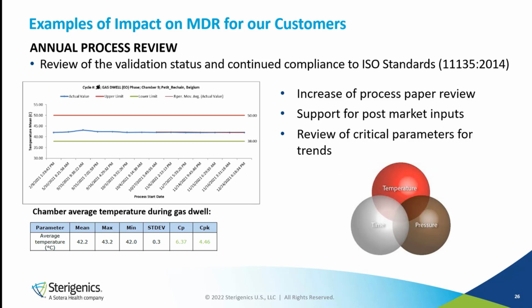Annual process review. So, as you mentioned, we have an increased scrutiny and request for post-market surveillance studies. Even once your product is on the market, you have to continuously provide data to ensure that your products are still compliant. What we have seen during the last 2 years is an additional request for us to perform process paper reviews. What is a process paper review? It's a review of all the most critical parameters of your cycle, and we are assessing if we are still under control and compliant. The reason we have been asked to provide more of those studies is that it's a great support for your post-market surveillance as part of the MDR.